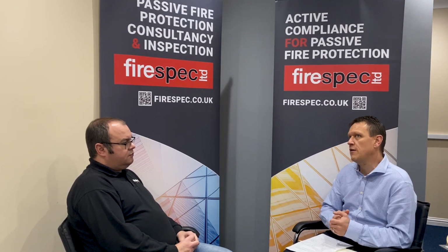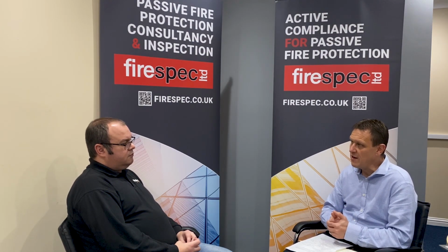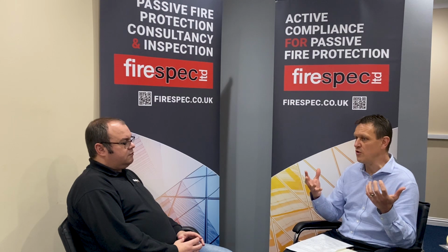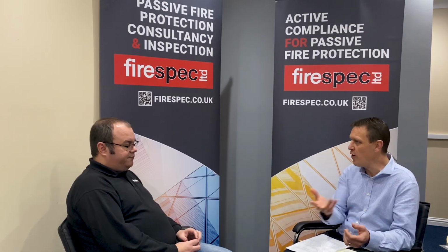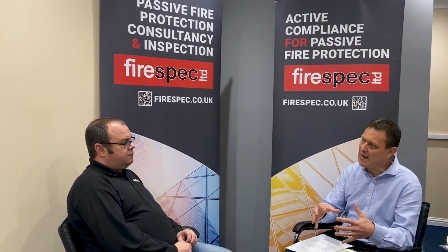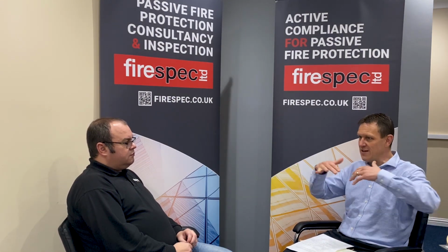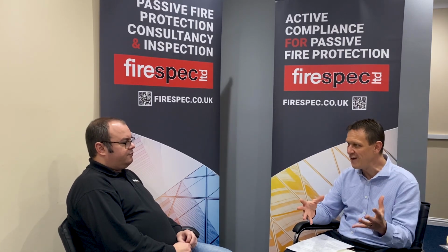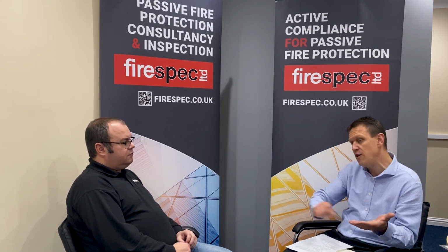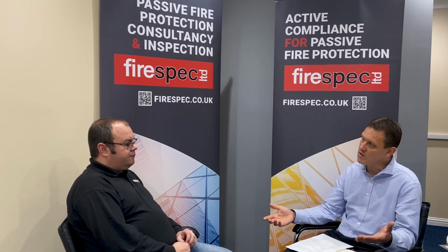Where these were all concrete construction and the walls are fairly defined, we've just finished working on one recently, and there were certain things where there was nothing they could do. It's a refurb. We're working on a number of refurbishment projects where they've stripped back to bare and gone back in, and there are aspects where, well, that's the opening you've got, that's the space we've got to work with, and there's literally nothing you can do with it. And it's like, guys, we can't sign off on that. All you can do is write in your report, this is the best fit, or this is the nearest you're going to get to a compliant solution. We know it's not tested.